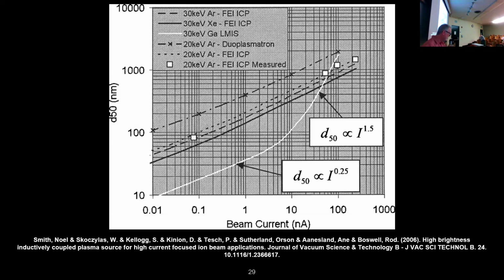So if you want to do lithography or make your life a lot easier for doing TEM sample preparation, a gallium machine is really nice to have. But once you get up in this view to around 50 nanoamps or thereabouts, the plasma becomes advantageous, where you have a much smaller beam size. And I find 60 nanoamps and 200 nanoamps on our microscope to be very good. Most dual beam gallium FIBs cap out at between 20 and 100 nanoamps somewhere, depending on the model.